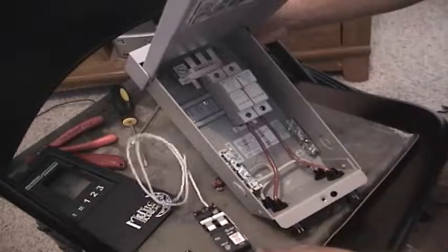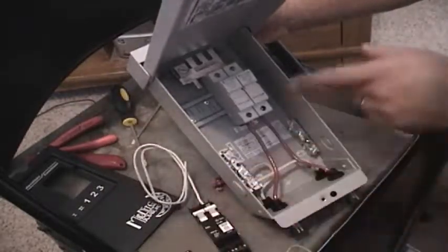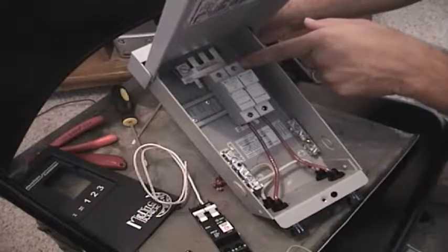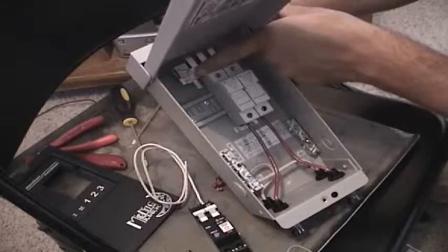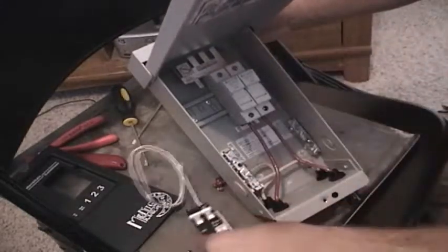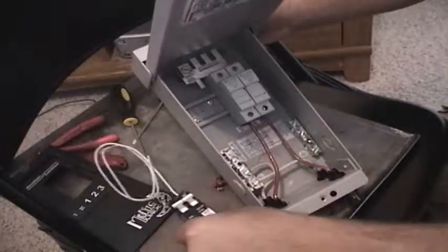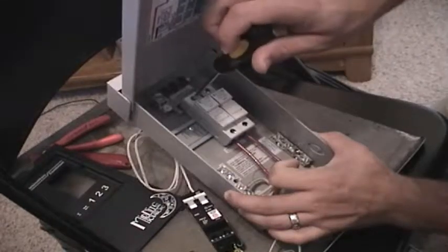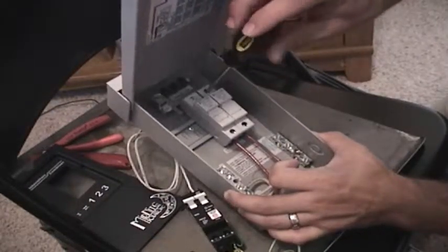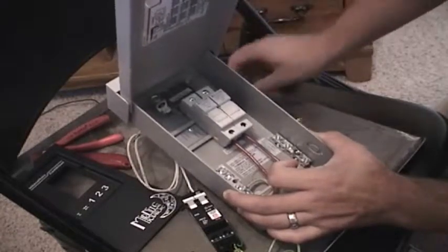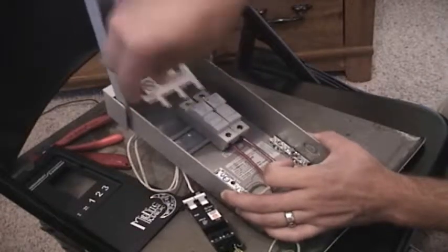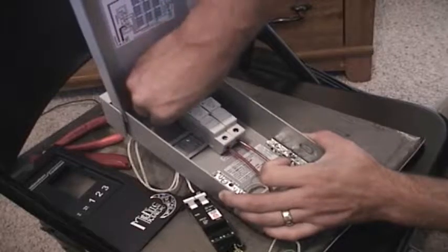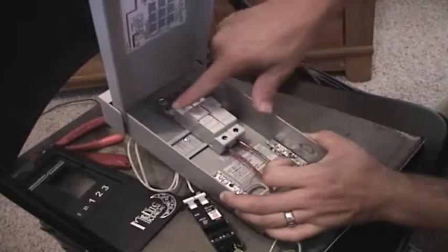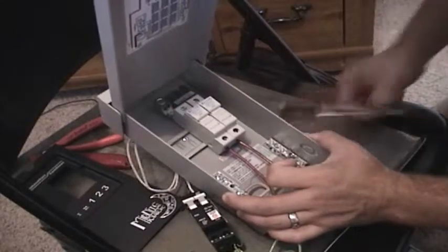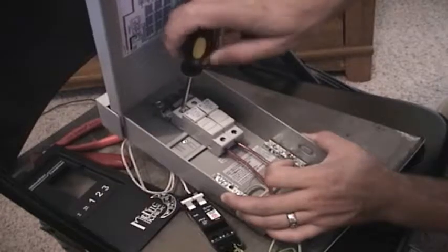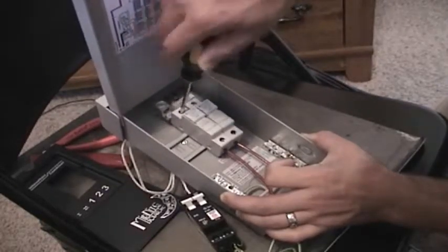In order to install the GFP device into the combiner box, we need to loosen the 2 top screws on the circuit breakers, and we need to shift over the tab on the PV out bus bar so that our GFP device can fit inside the box. Let's go ahead and do that now. Let's loosen the top screws on both of the circuit breakers, and then let's shift that bus bar over so that the tab is no longer sticking out to the side. And let's retighten the top screws on the circuit breakers.